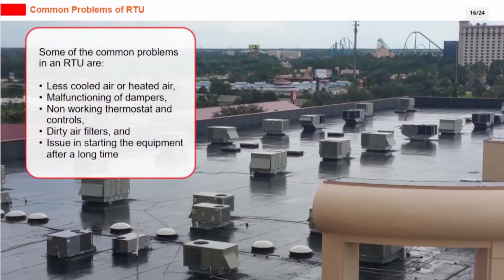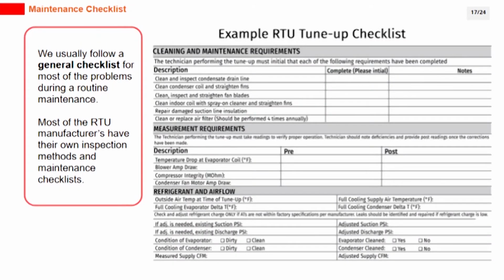Some of the common problems in an RTU are less cooled air or heated air, malfunctioning of dampers, non-working thermostat and controls, dirty air filters, and issues in starting the equipment after a long time. We usually follow a general checklist for most of the problems during a routine maintenance. Most of the RTU manufacturers have their own inspection methods and maintenance checklists.